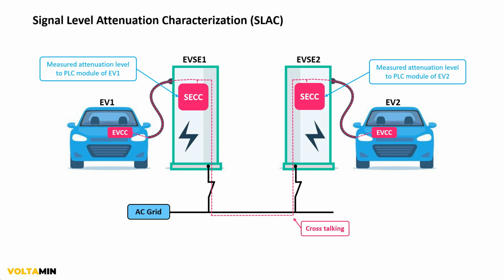In scenarios where multiple EVs are connected to nearby charging stations, crosstalk may occur between the connections. An EVSE will respond to SLAC requests only if it is connected to an EV, State B, and its PLC module is not already linked to another PLC module, indicating an unmatched state. How SLAC works: 1. Measuring attenuation levels across various signal paths. 2. Identifying the PLC modules that exhibit the lowest attenuation. An acceptable attenuation level in PLC modules is generally designed to be around 20 to 30 decibels. 3. Establishing the EV-EVSE connection by confirming that these modules are physically connected.